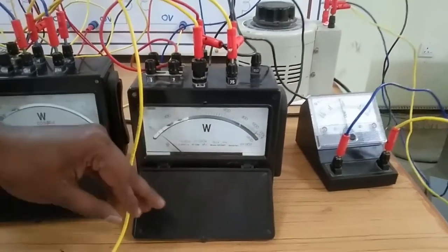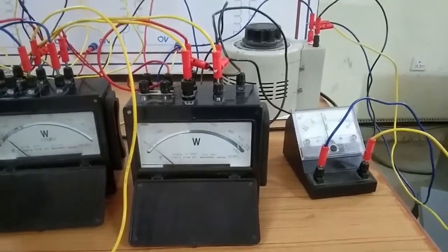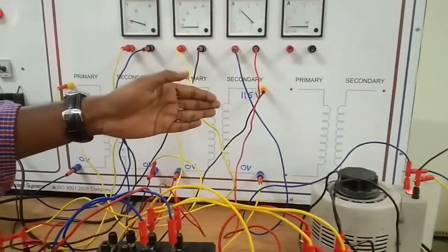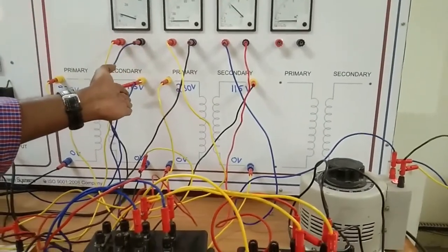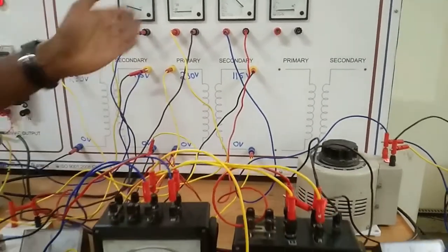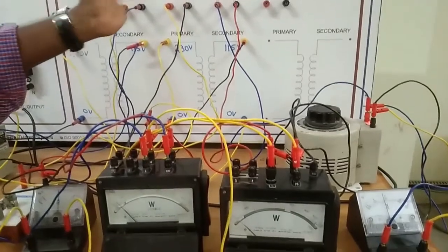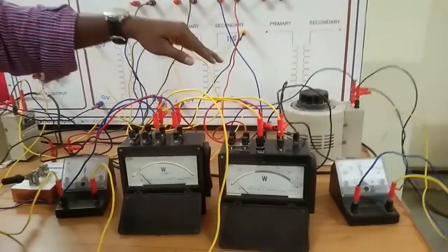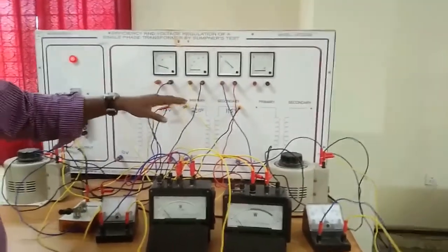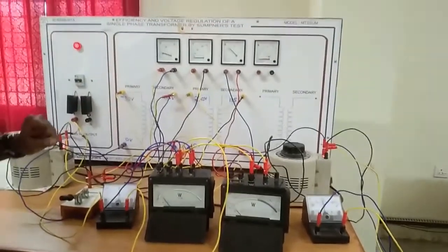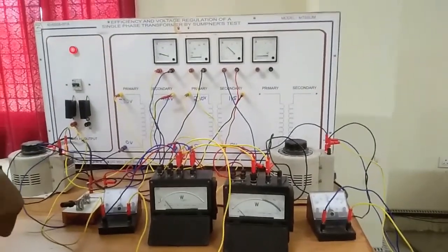So if you want to find the efficiency of any transformer, we have taken here two transformers connected back to back. If you want to find the efficiency of, suppose, the first transformer, then you separate the iron losses and copper losses for each transformer. Then you substitute in the efficiency formula, and you are able to get the efficiency of both the transformers at a time, right? So this is the advantage of the Sumpner test. Thank you.